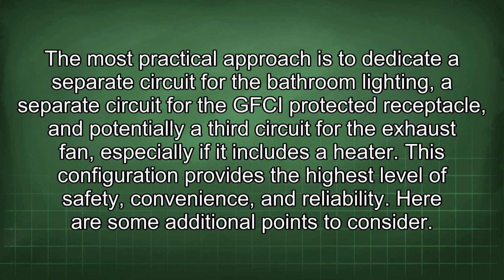The most practical approach is to dedicate a separate circuit for the bathroom lighting, a separate circuit for the GFCI protected receptacle, and potentially a third circuit for the exhaust fan, especially if it includes a heater. This configuration provides the highest level of safety, convenience, and reliability. Here are some additional points to consider.